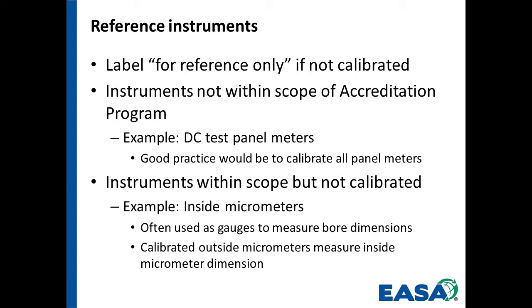Examples of instruments that could be used but not calibrated were the inside micrometers, where they're used as a gauge. You take the inside measurement and then you measure it with the outside micrometer that's calibrated. So you use that as a way of getting the measurement.